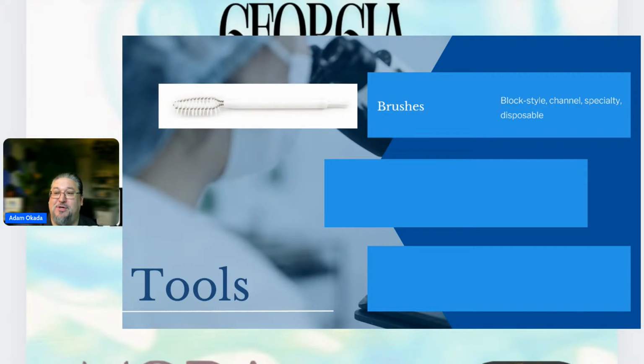So there was a big focus at the conference on arthroscopic shavers, and there are specialty brushes. You can see a shaver brush on the screen, specifically for that fork drive area. If you think about the shaver, it's got a long lumen, and then there's a fork drive at this end that's kind of poking out, and you have the lumen here. Your channel brushes are going to clean around this area. Same thing with the toothbrushes. They'll just clean this side, but nothing is going to be able to clean that fork drive. That's where you need a specialty brush to really get into those areas.